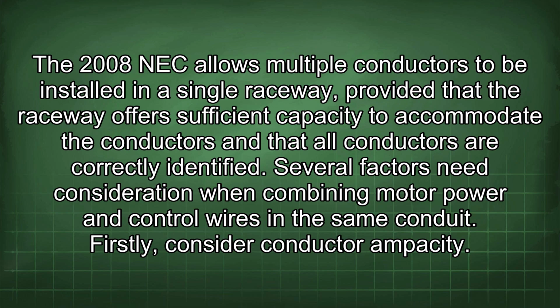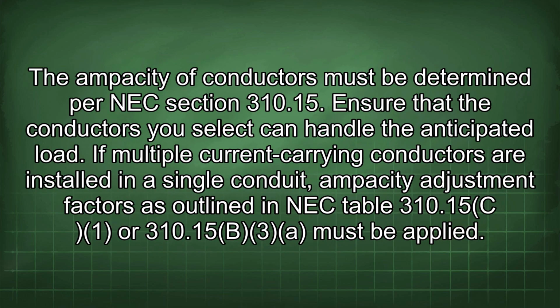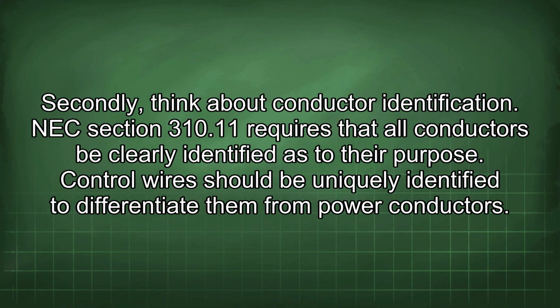Firstly, consider conductor ampacity. The ampacity of conductors must be determined per NEC section 310.15. Ensure that the conductors you select can handle the anticipated load. If multiple current-carrying conductors are installed in a single conduit, ampacity adjustment factors as outlined in NEC Table 310.15 or 310.15(B)(3) must be applied. Secondly, think about conductor identification.